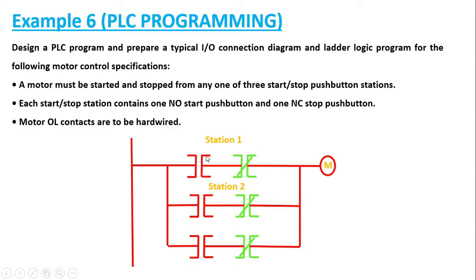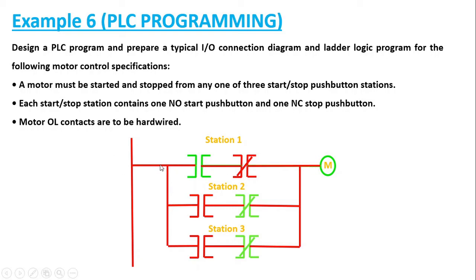If I press the start push button in station 1, it gets energized, and as indicated in green, the entire rung gets energized and the motor starts. So pressing the start push button of station 1 starts the motor — our logic is correct. Now if I press the stop push button, it becomes open circuit because it is a normally closed contact. The supply to the motor is cut off, the entire rung gets de-energized, and the motor stops.